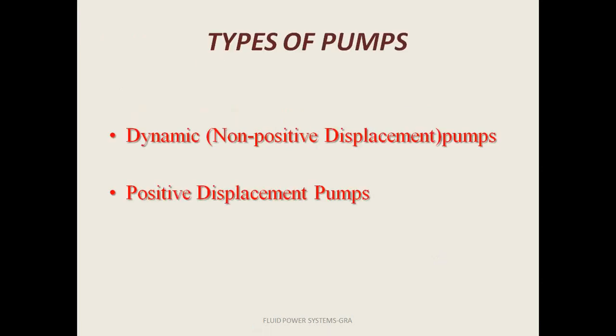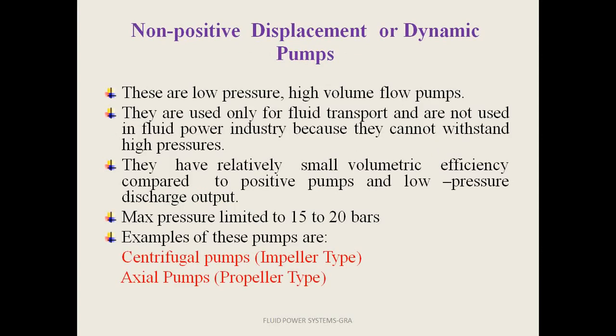Next, let us go through types of pumps. The first one is dynamic pump or non-positive displacement pump, and the second one is positive displacement. First, let us study non-positive displacement pumps. These are a few characteristics which I have listed. The first and foremost characteristic is that these are low pressure and high volume flow pumps. So these are used wherever high volume or high discharge is required and pressure is relatively low.